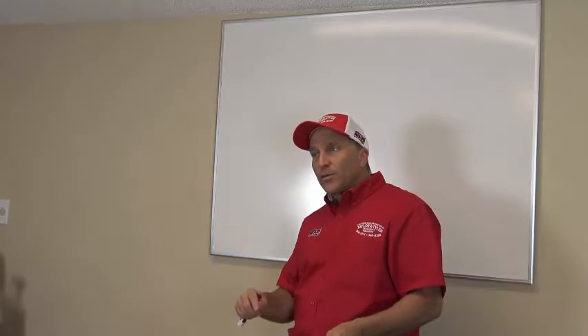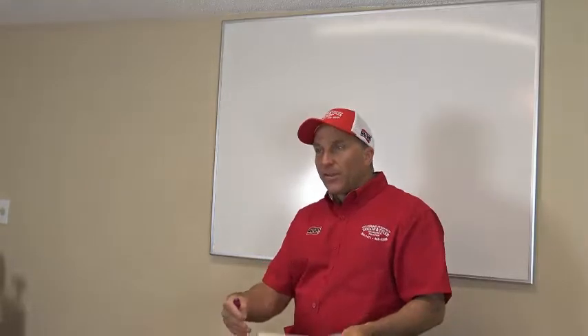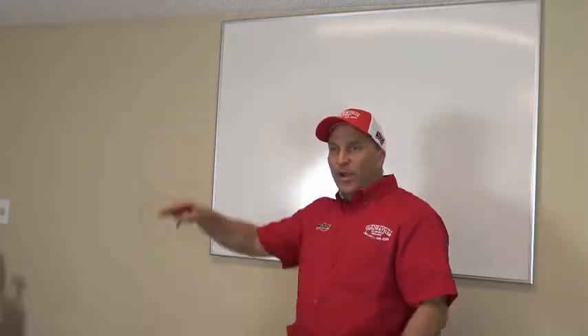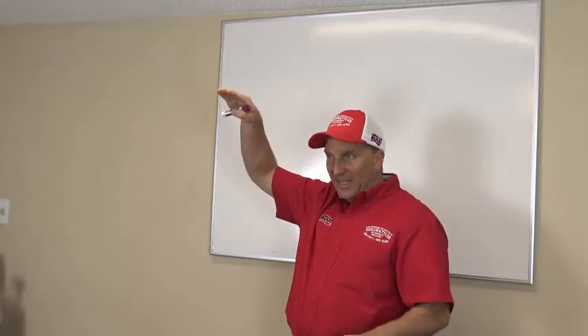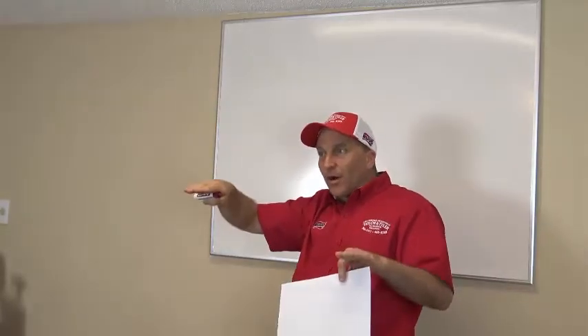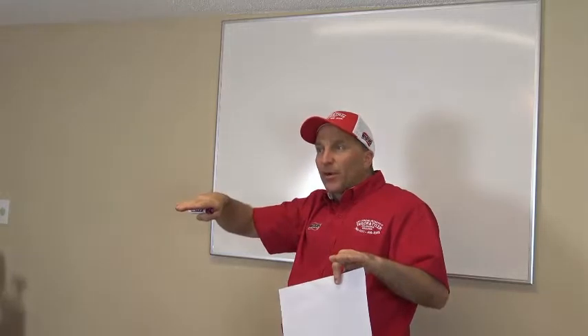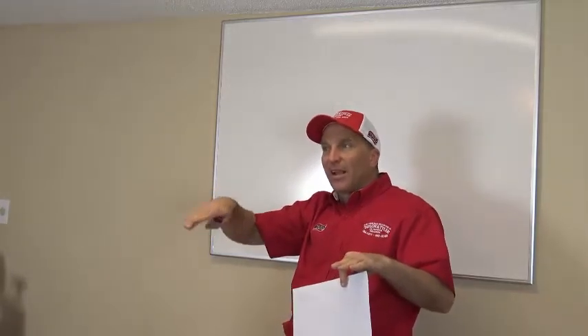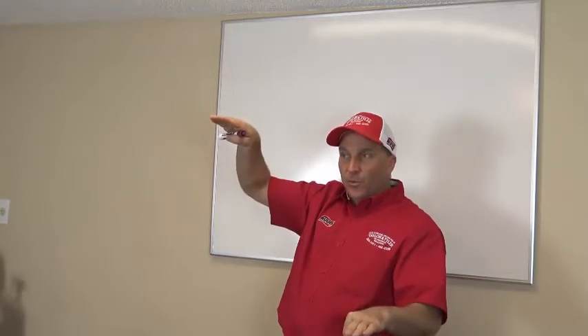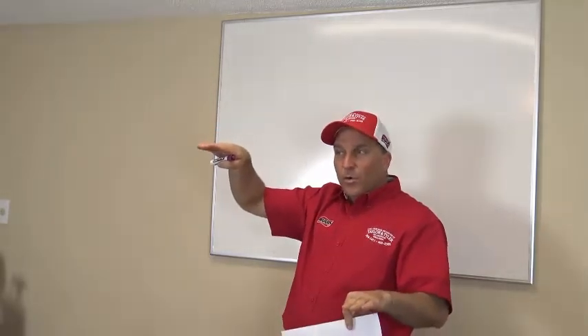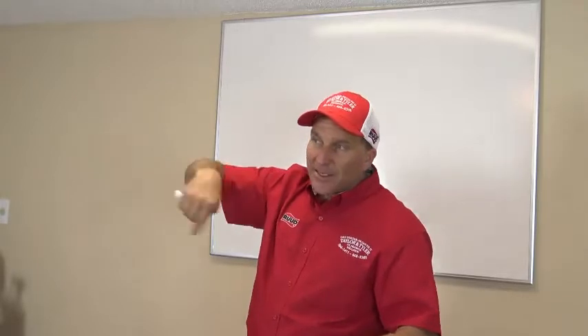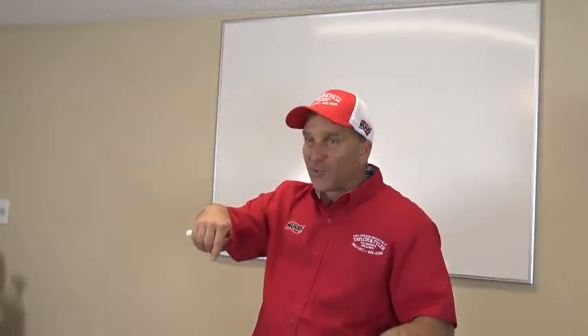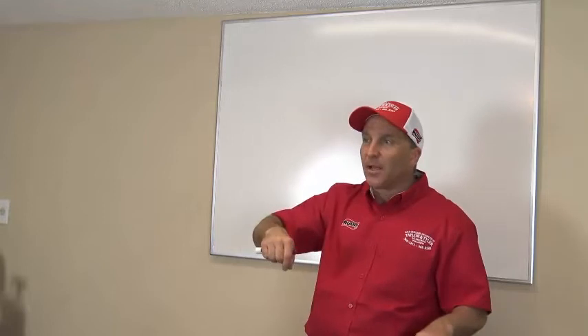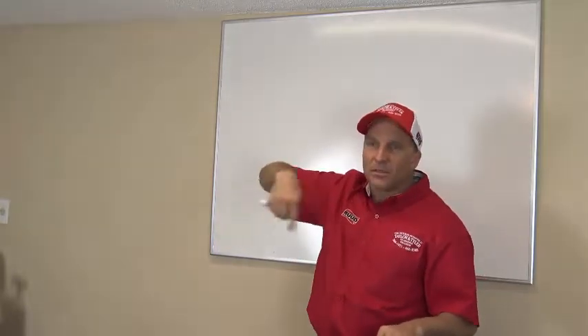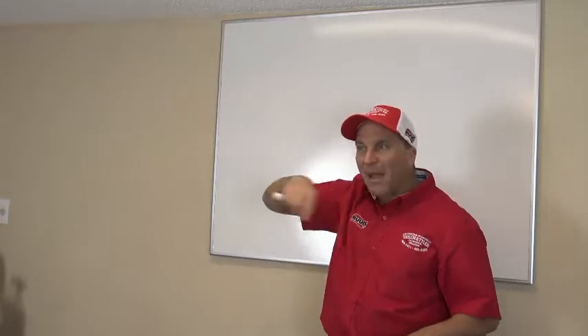And the scroll compressors actually can do a better job at starting and stopping real fast comparative to the old reciprocating compressors, where your head pressure and your suction pressure were unequal when it stopped, and it was hard for it to start. That's why with a reciprocating compressor, you always had a hard start kit on the system when it had a TXV, because your pressures remain unequal. With a scroll compressor, your compressor actually equalizes its pressure through the compressor. That's why you'll hear that sound when it goes and stops. That compressor is basically allowing it to run backwards.